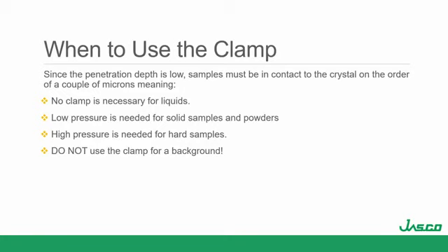Remember the path length is very small, and the gases in air are at a much lower concentration than what you're going to see in your sample. So you don't need to put the clamp down for the background.